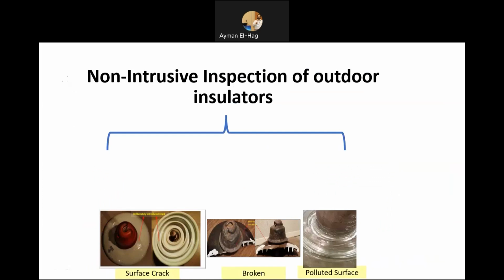Now, as I mentioned, the failures can be classified as electrical and mechanical, but they stem from some faults that happen in the insulator, and they escalate until we have a complete failure. So for example, for the mechanical failure, these are some cracks that will actually trigger some discharges, and if these insulators are not inspected at an early stage, they might get broken, and then mechanically the whole line might fail. On the other hand, you could have a polluted surface. A polluted surface can lead to some discharge on the surface, and that can lead to the complete electrical failure of the insulator.